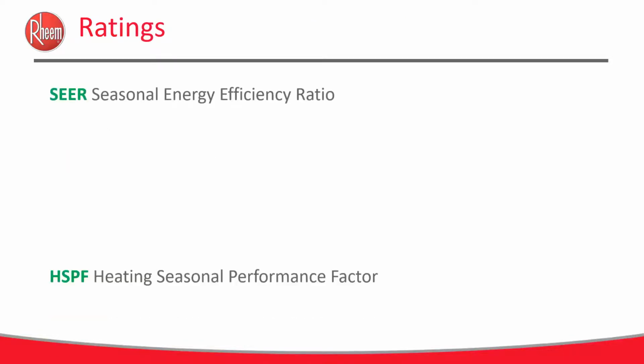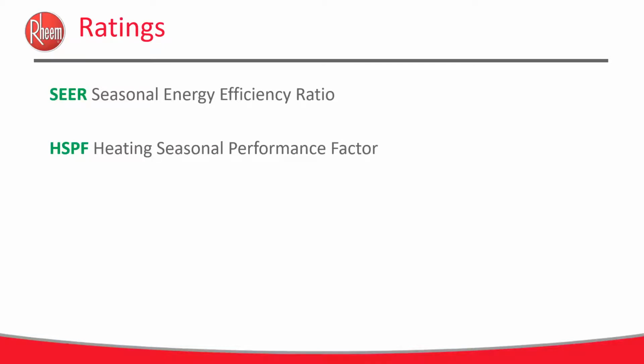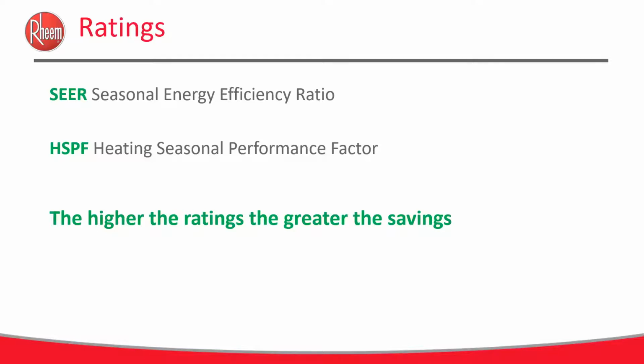Just some of the terms that we will cover: seasonal energy efficiency ratio, by which ACs and heat pumps are measured. SEER determines expected energy efficiency for the whole season. So the efficiency of the AC is measured at air temperatures from 65 Fahrenheit to 104 Fahrenheit. This also accounts for the stopping and starting of the unit. Heat pumps are rated by heating seasonal performance factor when in heating mode, and 8.5 today earns you an Energy Star rating. When heat pumps are operated in cooling mode, the unit's efficiency is rated by SEER. The higher the ratings, the greater the savings.